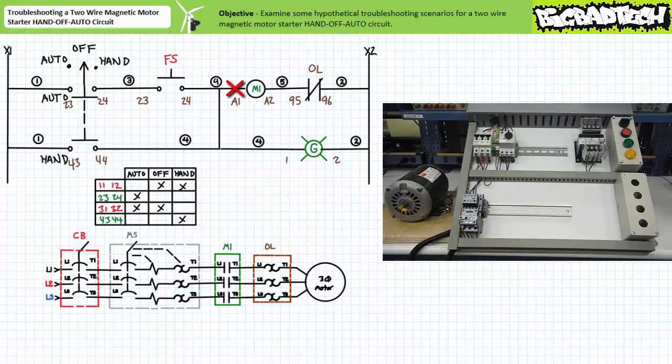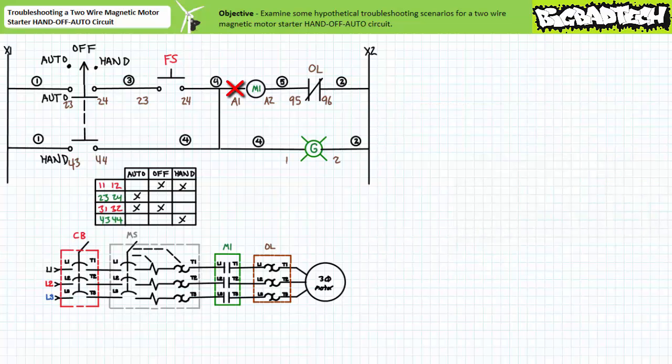Consider this circuit where I've purposely disconnected all wires leading to the A1 terminal of the M1 contactor coil. Neither the auto mode with the simulated float switch closed, nor the hand mode serves to start the motor. What's a technician to do? Obviously, the correct answer is to fix the system and wire the system as intended.